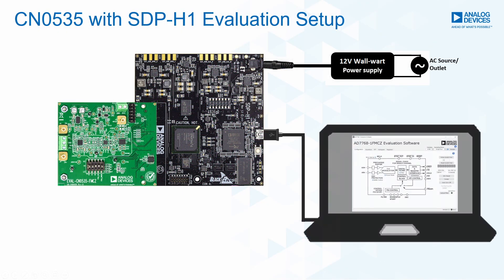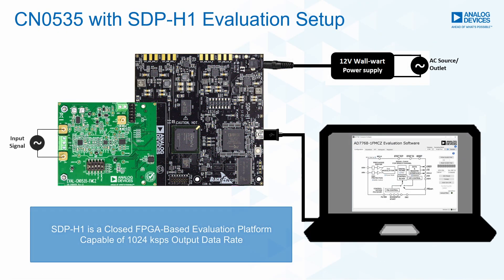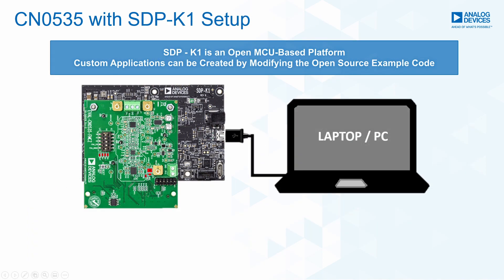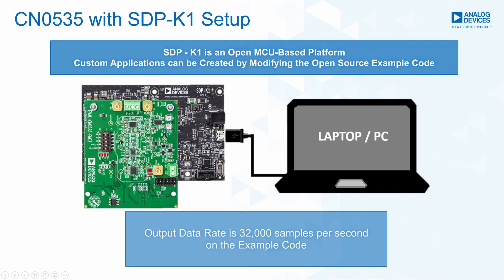Originally, it was designed to be evaluated using SDP-H1 and the LabVIEW-based evaluation software. It is important to take note that if we use the SDP-K1 and MCU-based platform, the throughput of the ADC will be limited.